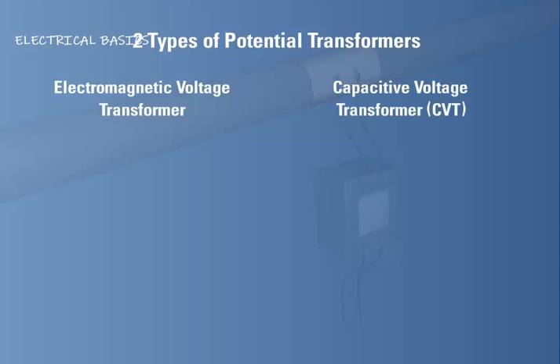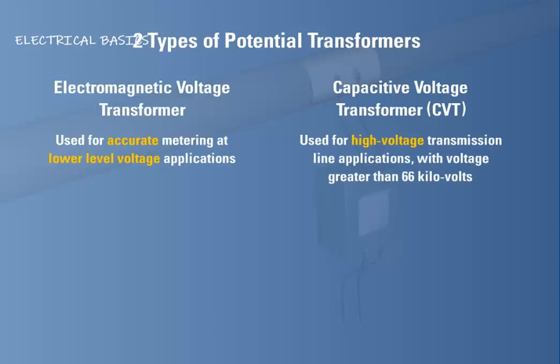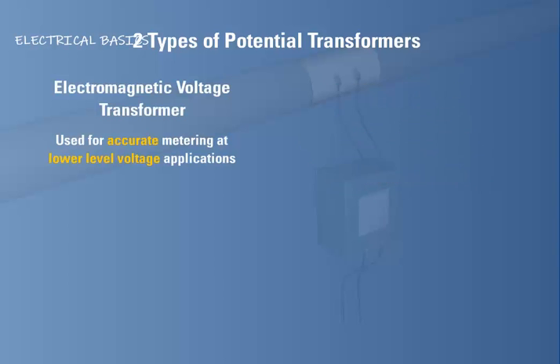Electromagnetic voltage transformers are usually used when accurate metering needs to be performed for lower voltage applications. Capacitive voltage transformers are commonly used in high voltage transmission line applications where the voltage is higher than 66 kilovolts.